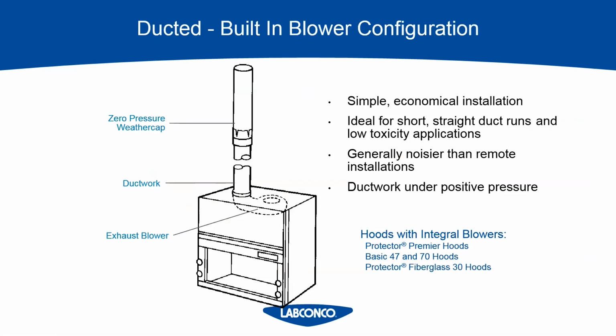And the biggest reason against using a built-in blower is that it puts all of the ductwork under positive pressure. So the entire length of duct from the fume hood up to the termination, basically up on the rooftop, is having air pushed through it rather than being pulled. And so going back to that example in the office space, if you had a leak, it's going to just send that contaminated air through that leak because it's under positive pressure.